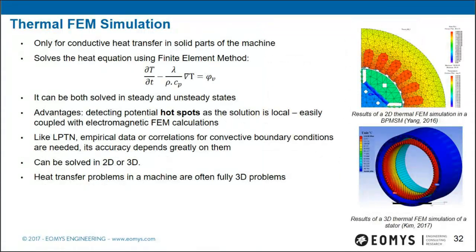The second method is finite element simulation of the solid parts of the machine, solving the heat equation directly on those parts. Its main advantage is local resolution, allowing detection of potential hotspots. It is also easily coupled with electromagnetic FEM calculations. Like LPTN, it requires empirical data or correlations for boundary conditions, and result accuracy depends greatly on them. It can be solved in 2D or 3D — but unlike electromagnetic problems, heat transfer problems are often inherently 3D.